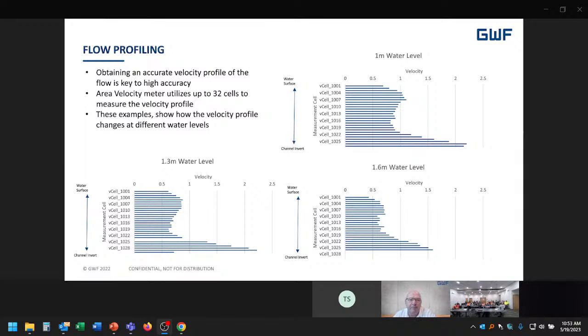The surface is at the top, the bottom of the channel is at the bottom, and we've got three different data points we can show. You can see the velocities differ depending on where you measure within the channel. The radar and laser sensors tried before only measure at the very top, and you can see higher velocities towards the bottom, meaning point-contact measurements were likely quite wrong. We calculated about 40% uncertainty based on a spot measurement at the top of the flow.